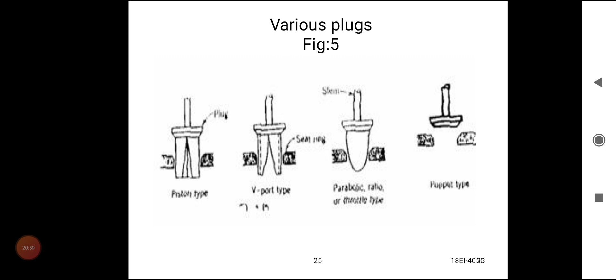Piston type plug valve, V-port type, parabolic ratio or throttle type, poppet type. The plugs are of various types: piston type, V-port type, parabolic ratio type or throttle type, poppet type. These plugs are attached to the stem. According to the movement of the stem, the plug moves around the valve seat, so that tight closing or opening can be done.